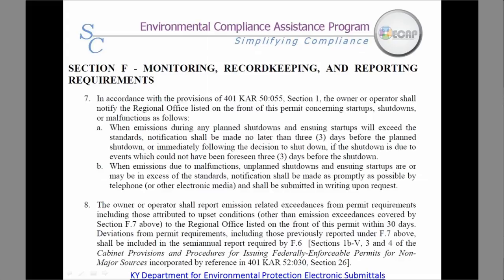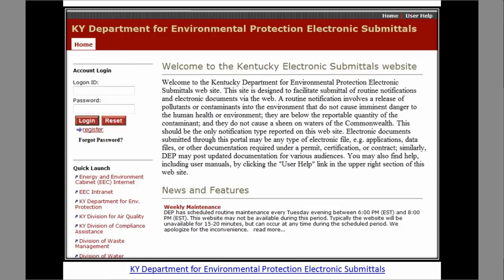For notifications, you may contact your regional office inspector or, preferably, submit routine notifications electronically on the DEP gateway.ky.gov portal. A routine notification includes release of pollutants or contaminants that do not cause imminent danger to human health or the environment, where the release is below the reportable quantity and does not cause a sheen on the waters of the Commonwealth. Notifications are only required if a planned startup or shutdown expects emissions to exceed the standard. For unplanned startup, shutdown, or malfunctions, a facility must notify when emissions are or may be in excess of the standards. Do not submit a notification every time there is a startup, shutdown, or malfunction if there are no excess emissions and no reason to expect any.